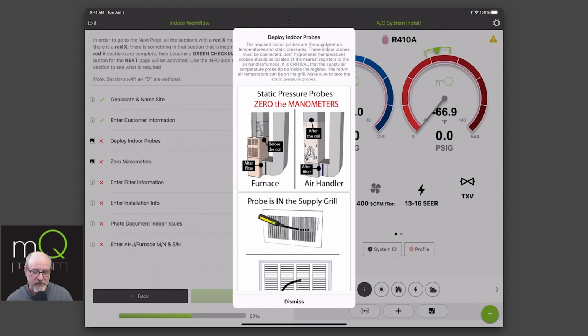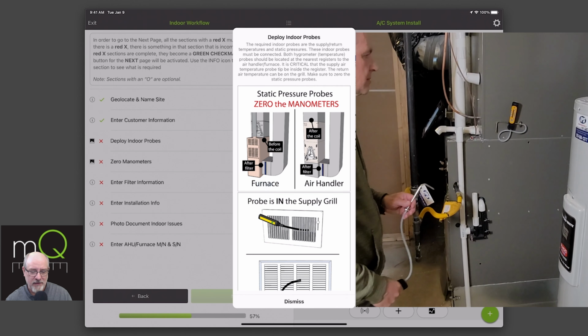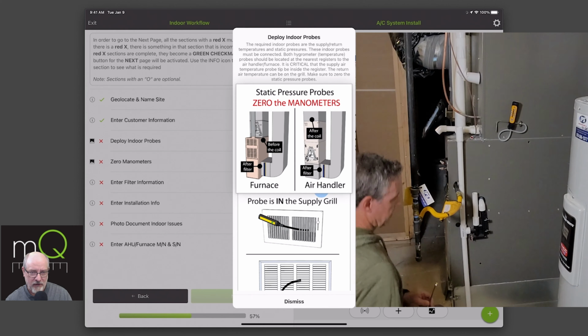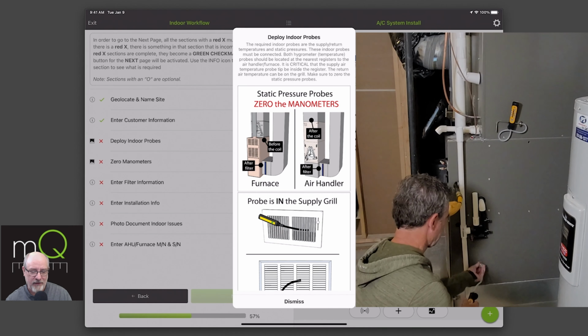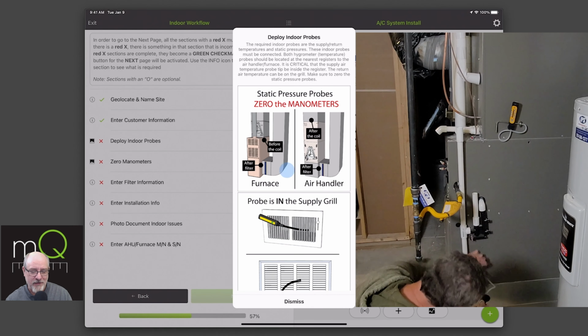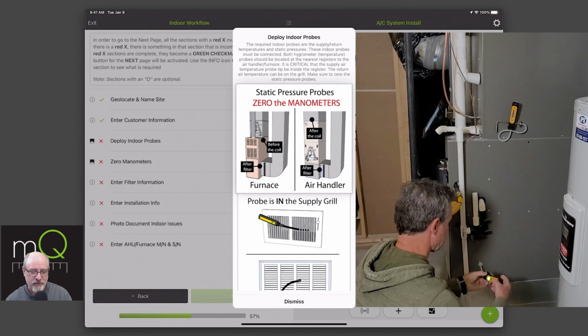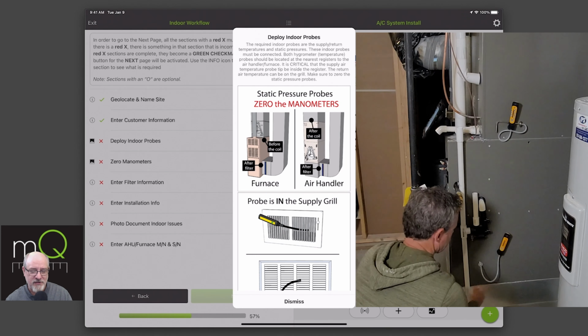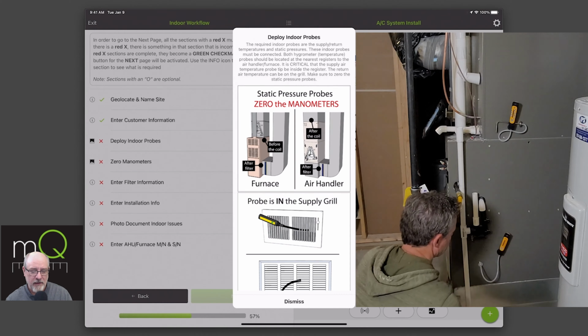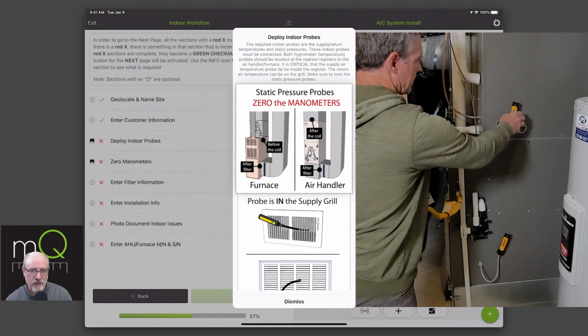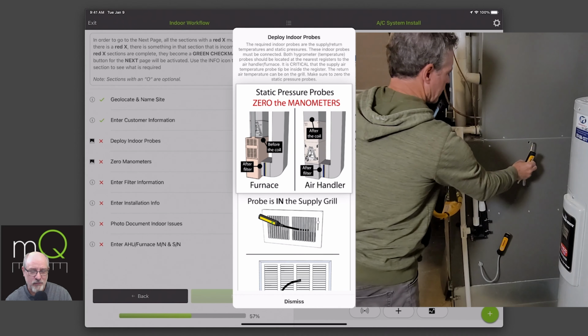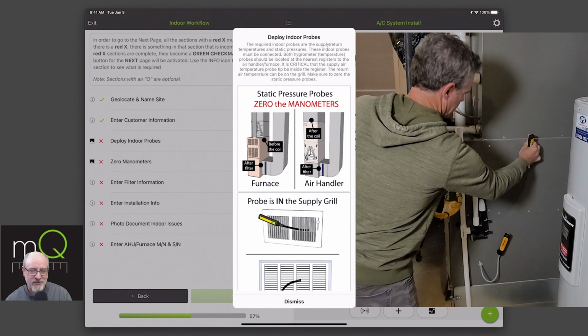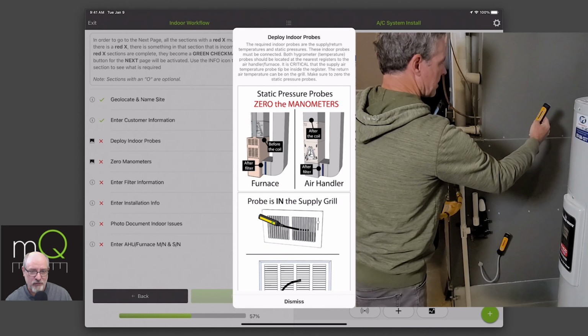It's the first time doing this, or a reminder for newer technicians: it's important to understand, when placing your manometers for static pressure, the difference between a furnace and an air handler. They are quite different if you really want to measure accurately. Both have the same concept briefly: they're always after the filter. The furnace is before the coil, and the air handler is after the coil. It's all about what's in the box when you take it out and install it, which one's an accessory, and which one's included in the actual system.